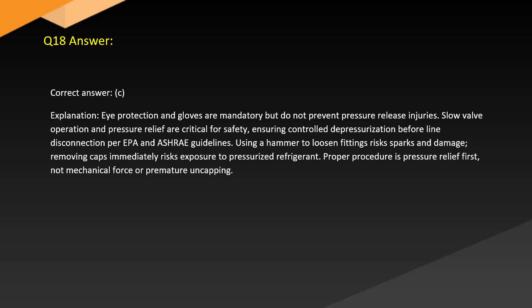Answer. Correct answer: C. Explanation. Eye protection and gloves are mandatory but do not prevent pressure release injuries. Slow valve operation and pressure relief are critical for safety, ensuring controlled depressurization before line disconnection per EPA and ASHRAE guidelines. Using a hammer to loosen fittings risks sparks and damage. Removing caps immediately risks exposure to pressurized refrigerant. Proper procedure is pressure relief first, not mechanical force or premature uncapping.